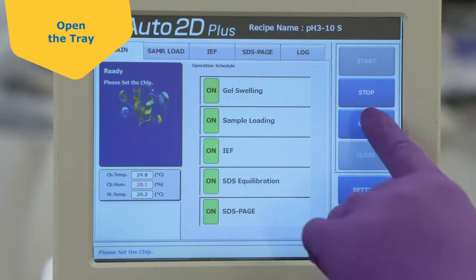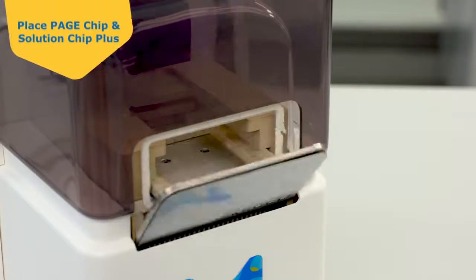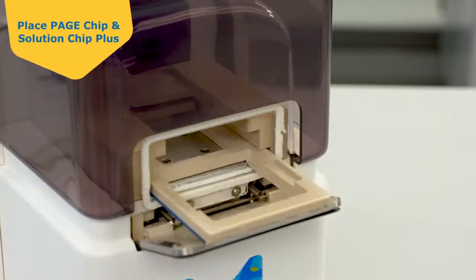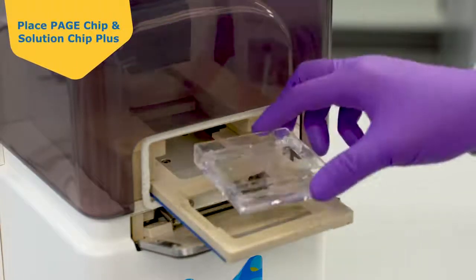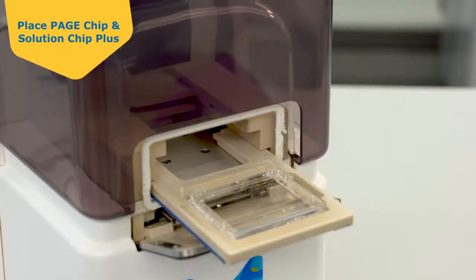Touch the Open button and OK on the screen to open the tray. Set the PAGE chip into the tray with the anode side towards the front. If the PAGE chip is inserted incorrectly, it will not sit flush in the tray.